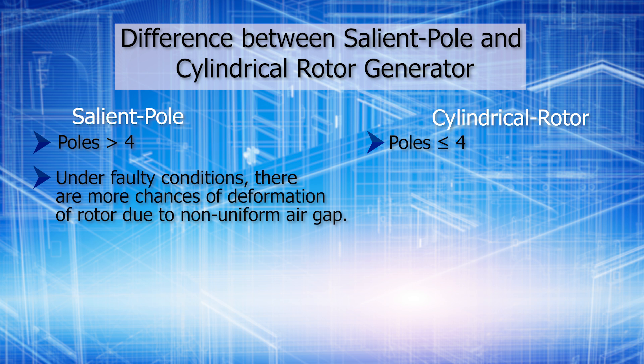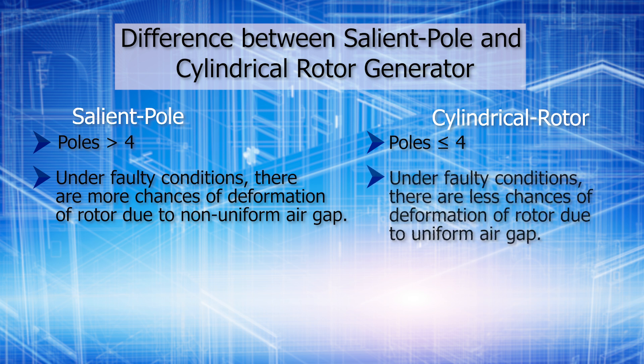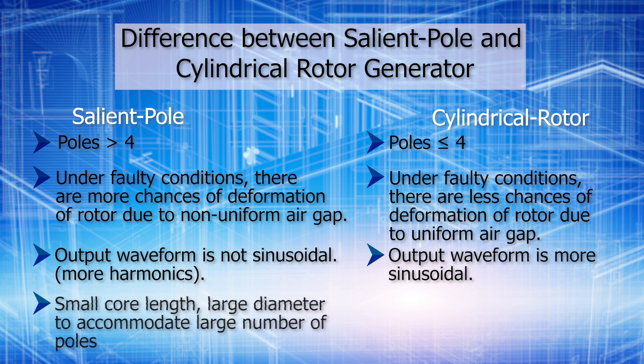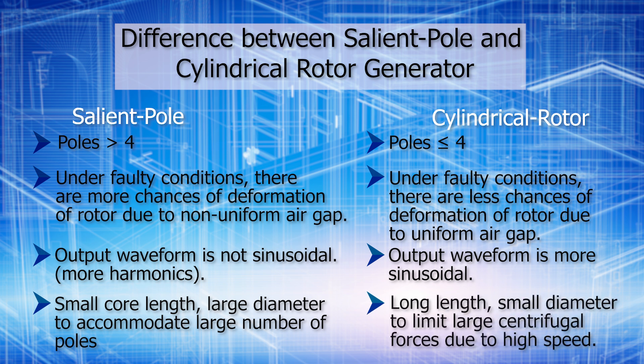In salient pole, the output waveform is not sinusoidal — there are more harmonics and the shape is distorted. In cylindrical rotor, the output waveform is more or less sinusoidal. In salient pole, we have small core length and large diameter to accommodate a large number of poles, whereas in cylindrical rotor we have long length and small diameter to limit large centrifugal forces due to high speed.